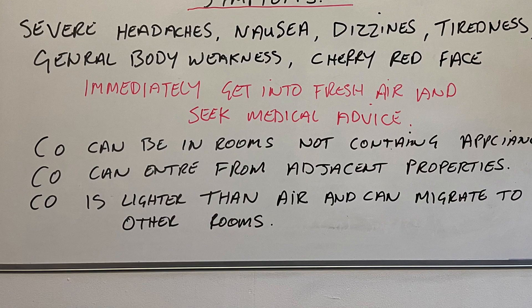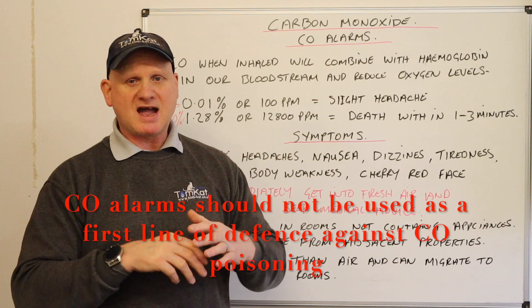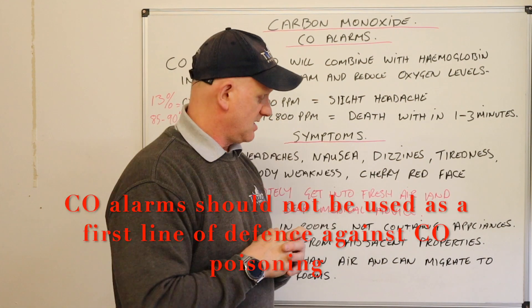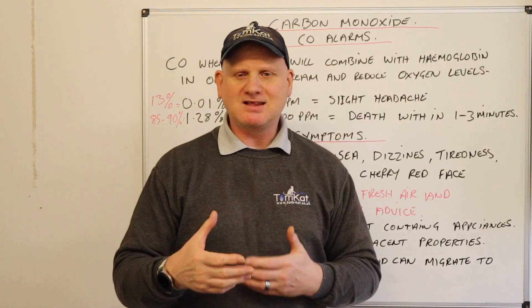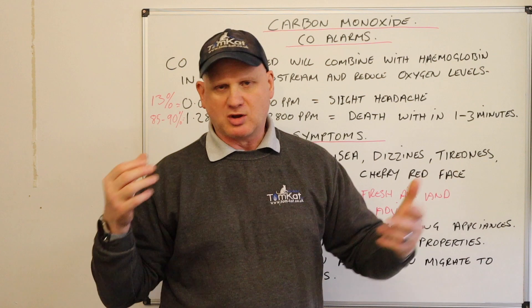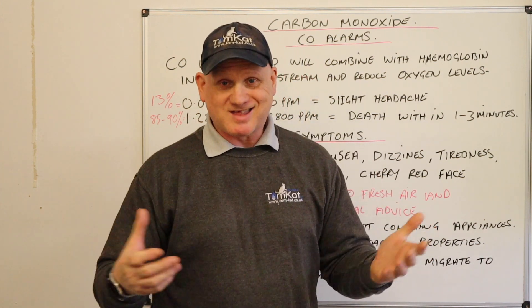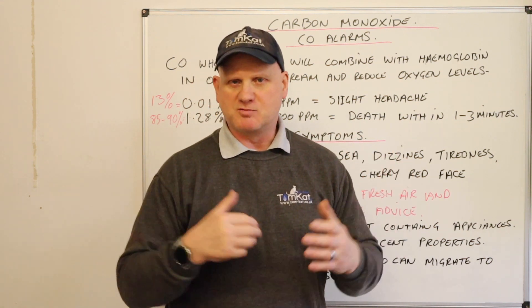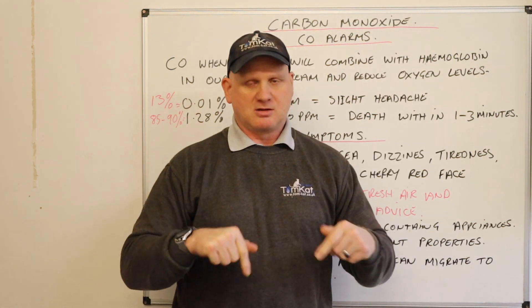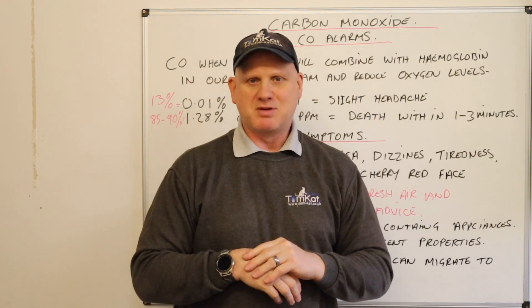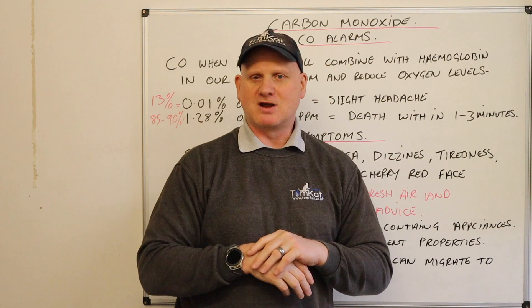CO can enter the room from adjacent properties, so CO alarms could be activated from next door on either side. CO is lighter than air once it's been burnt — that's when it becomes lighter. Its actual density at room temperature is the same as air, so it will hover around, but coming from an appliance it's at a higher temperature and can migrate through cracks in doors or even floorboards. You could be burning a fossil fuel appliance downstairs, be in bed, and still get carbon monoxide from it. The staircase is also a good route for CO migrating through the building.